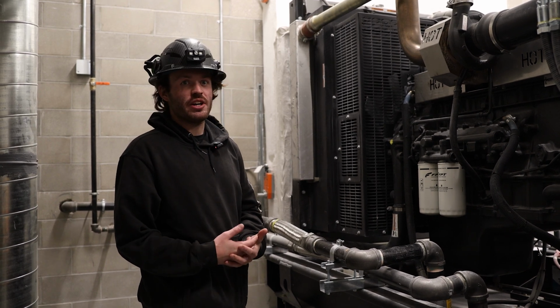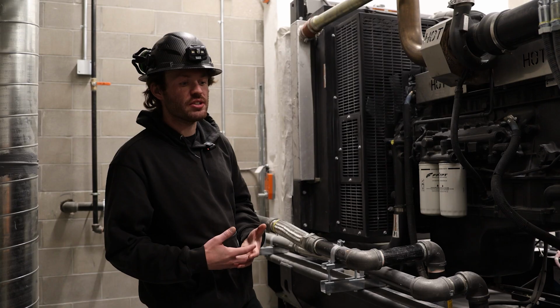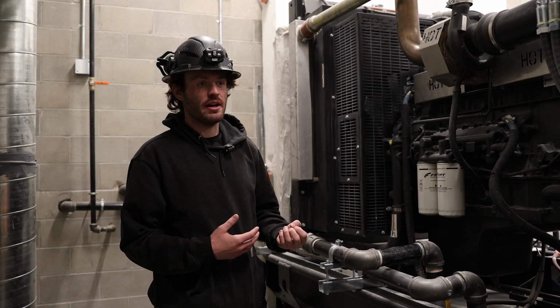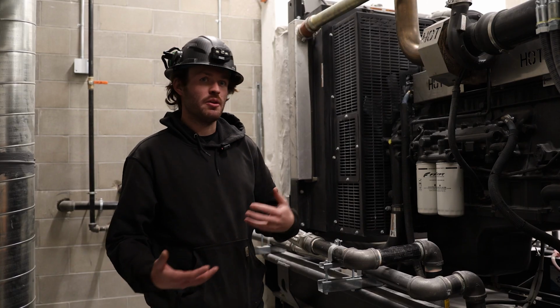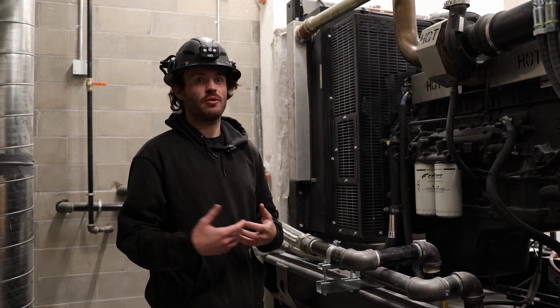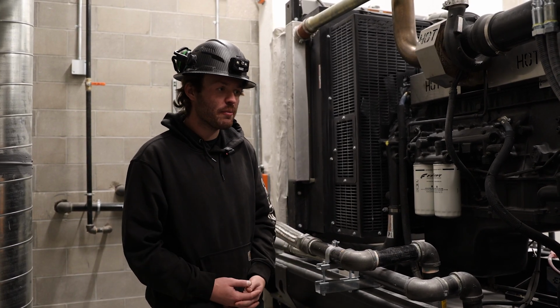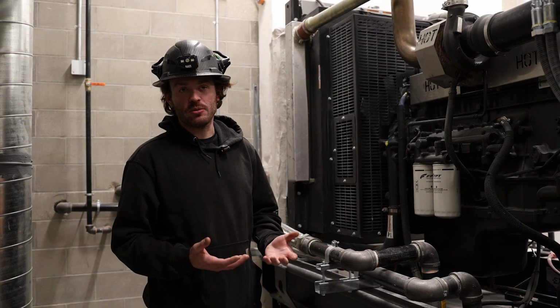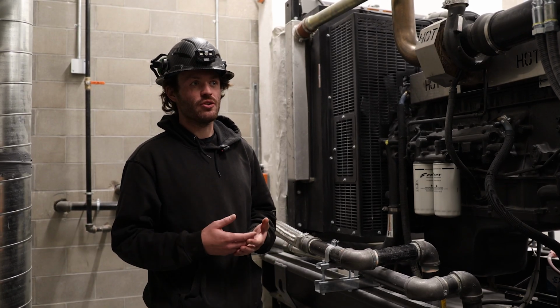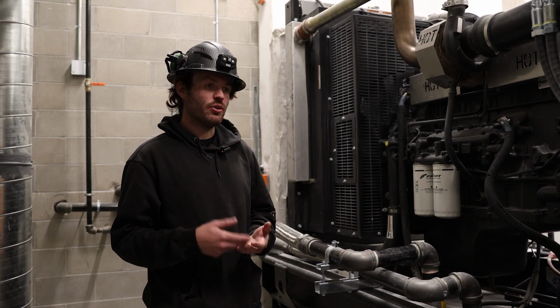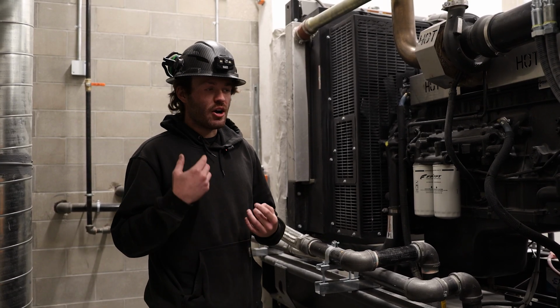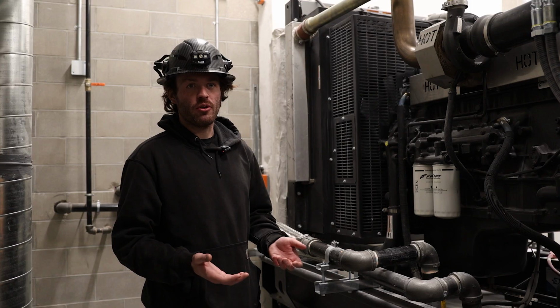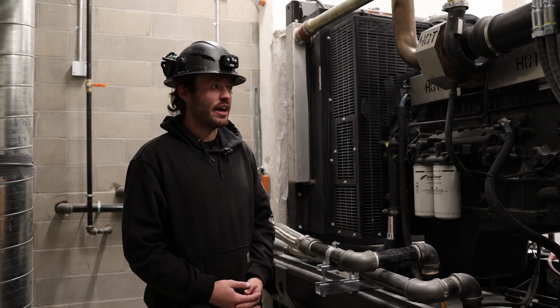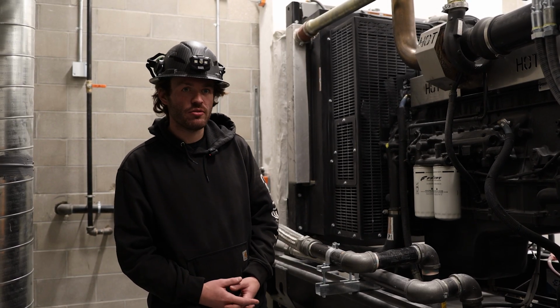Engine oil should be changed once a year. By code, it is mandated that that's to be done by a certified generator service technician, whether a company like myself or one of the other companies that does it in the area. At that time, on what's called the annual service, the engine oil filters, fuel filters, and a comprehensive inspection of the unit will be performed, including load testing of the batteries and load testing of the generator itself.